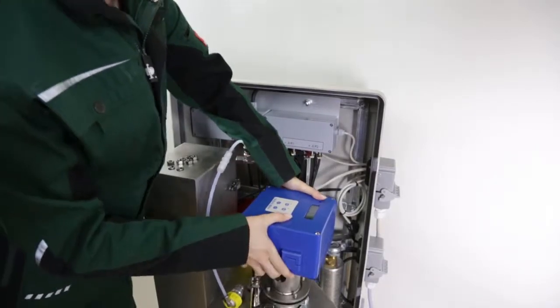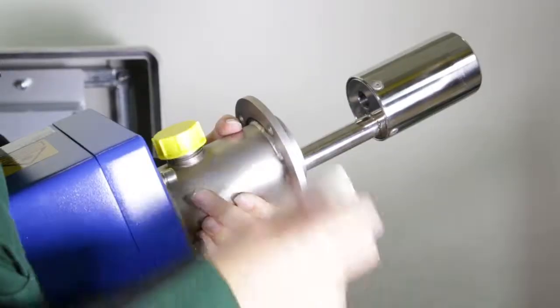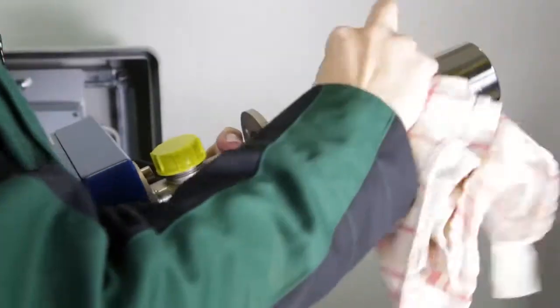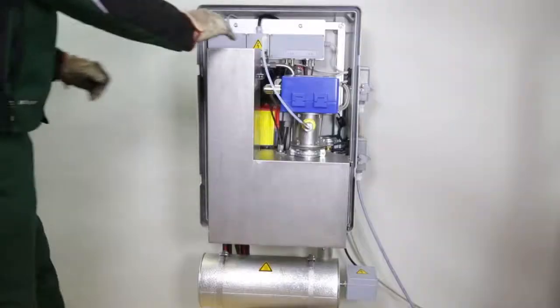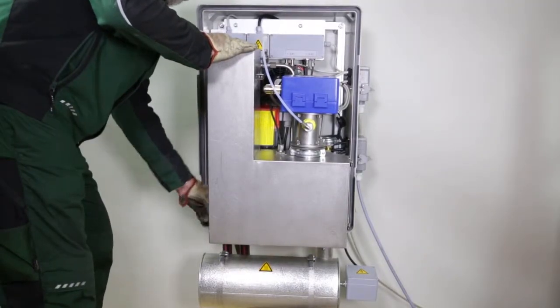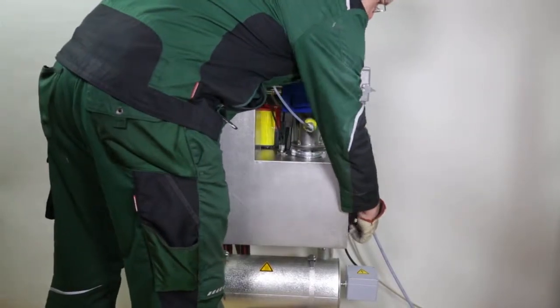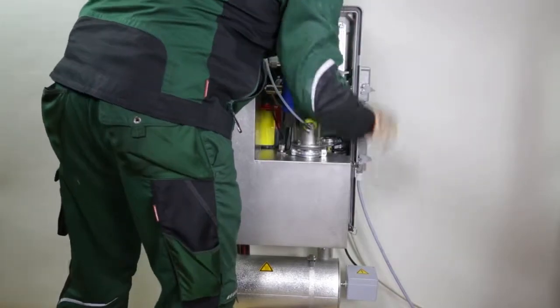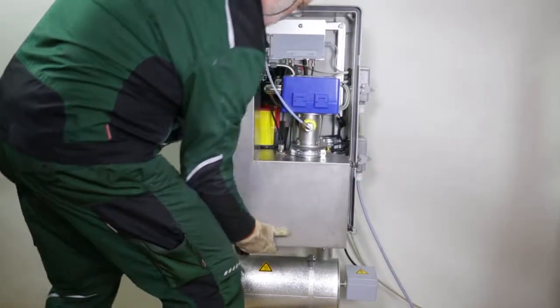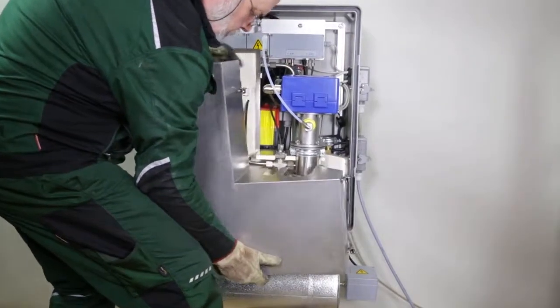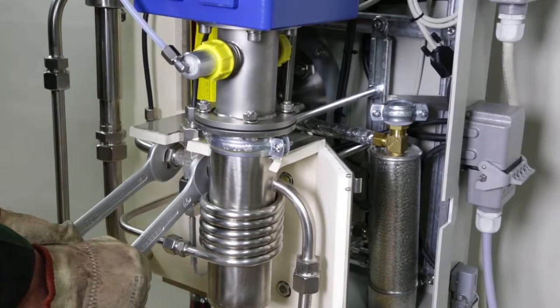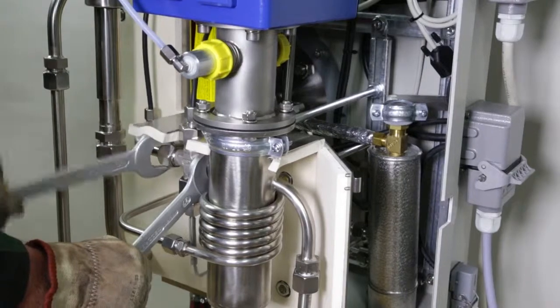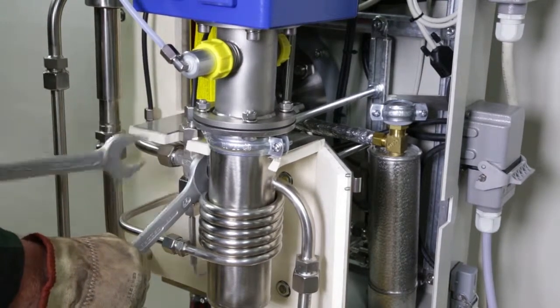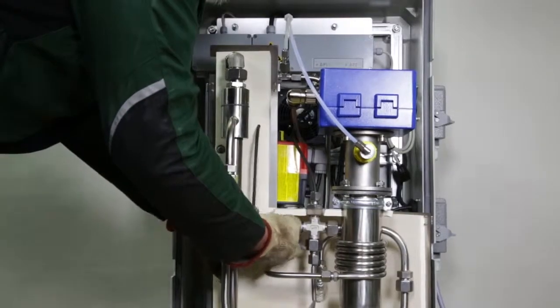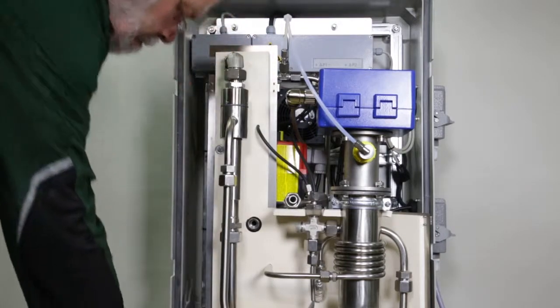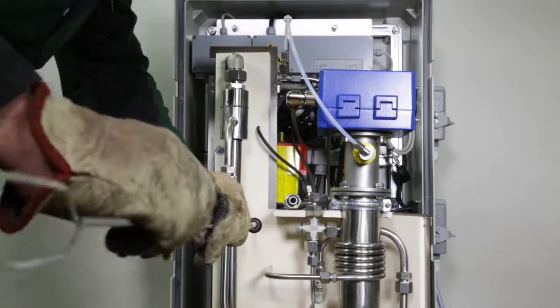Disassemble the optical sensor. Clean the optical sensor with a clean cloth. Release and remove the isolation in order to clean the sampling tube. Remove the bow between ball valve and measuring chamber. Clean the sampling tube with the cleaning brushes.